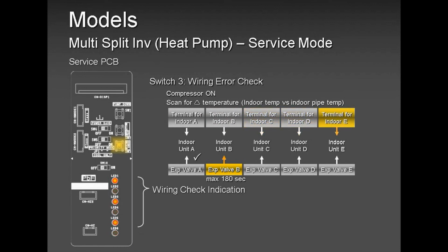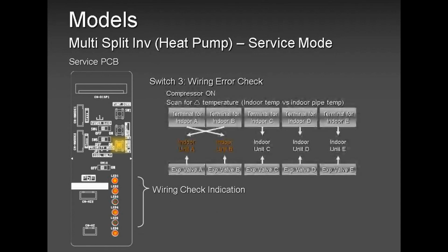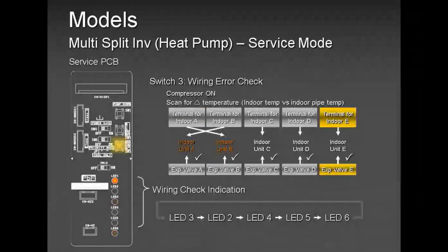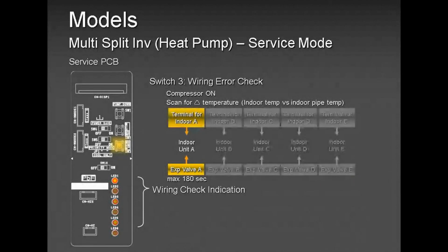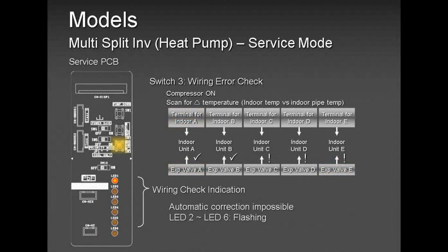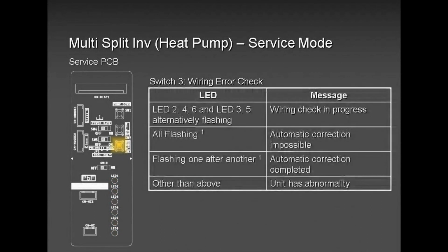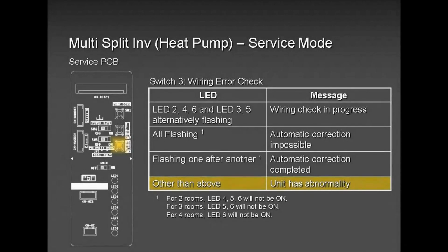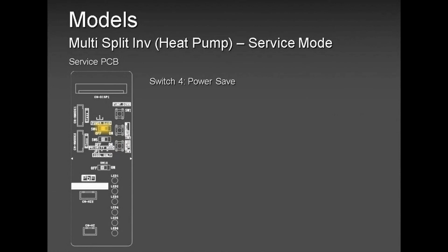So that's a good way of testing if you crossed your wires. I understand sometimes when the guy is about to do his wiring, he gets a phone call, and that phone call maybe was not good, or maybe it was too good, and they get confused and cross the wires. It happens. So this is the best way I do it: one unit at a time, I run it for 5-10 minutes, I'm happy, I switch it off, and I go to the next. Test run is good when you have a problem. When the customer is calling and complaining that it's not heating the way they want, or it's not cooling well, test run is good.